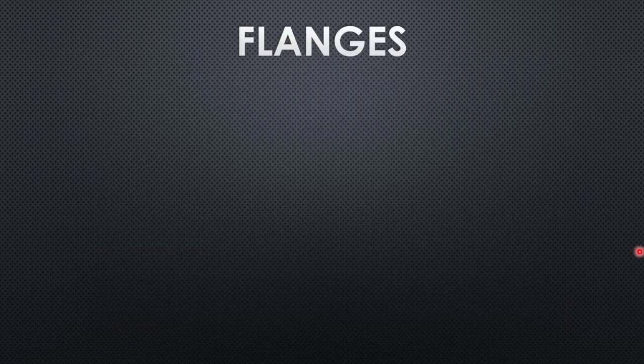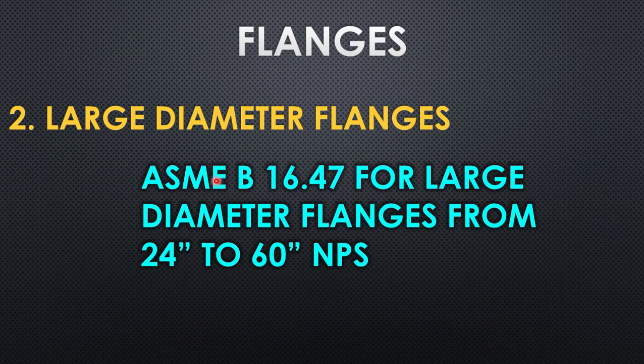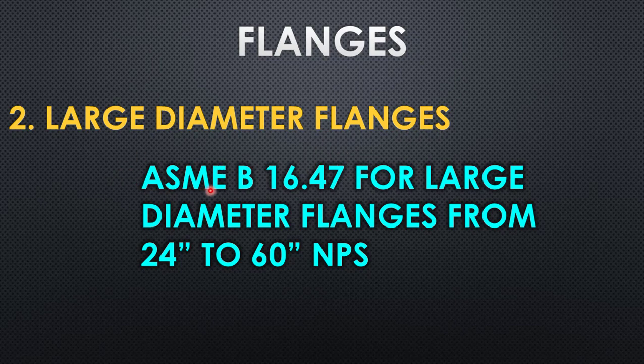Now let's go to the second category — large diameter flanges. These are classified into two types because the dimensions are completely different for flanges above 24 inch, which is one reason why two different standards are made. The large diameter flange dimensional standard is ASME B16.47, and the description is large diameter flanges for 24 to 60 inch. The constraint is that this standard only covers up to 60 inch — not above.